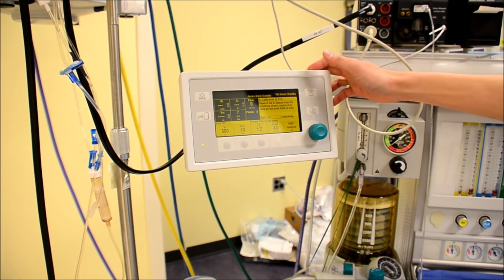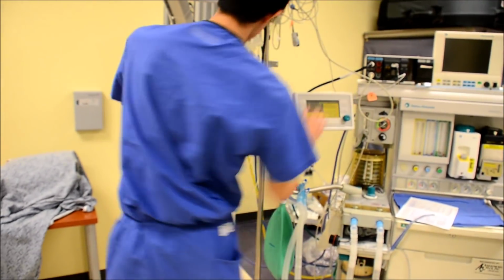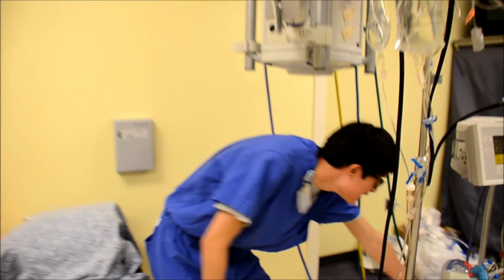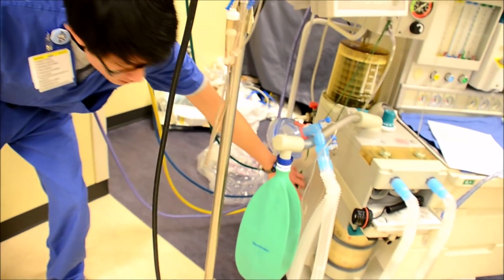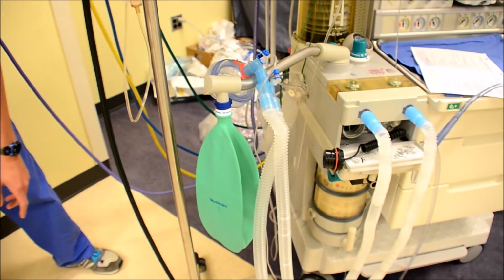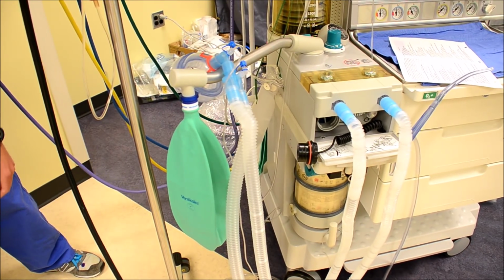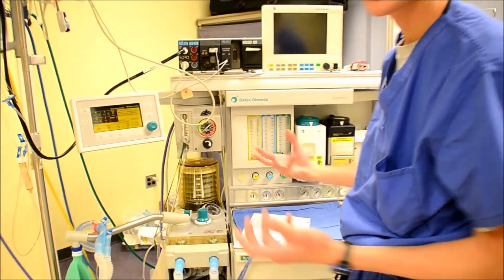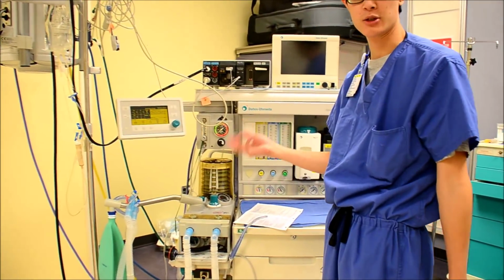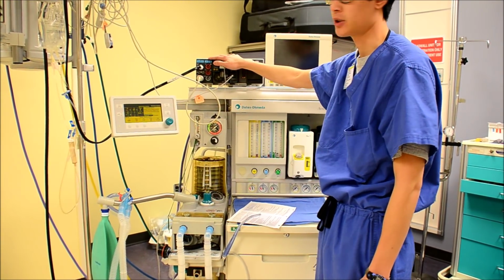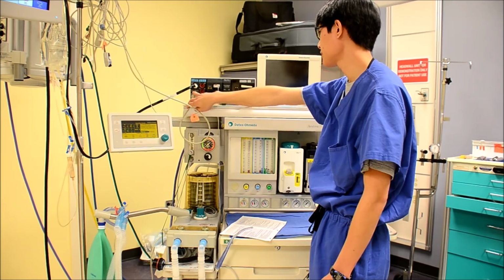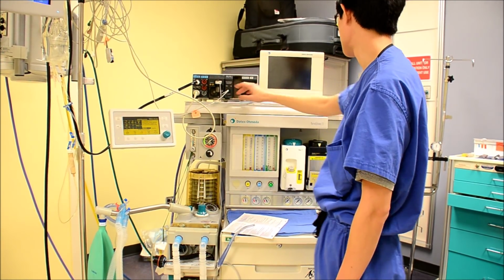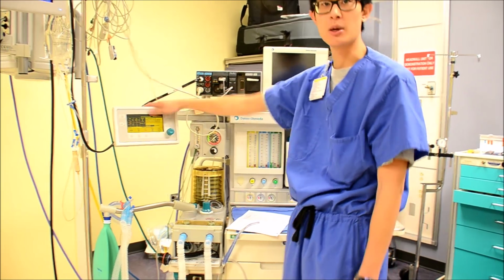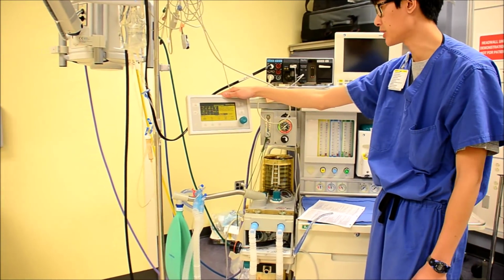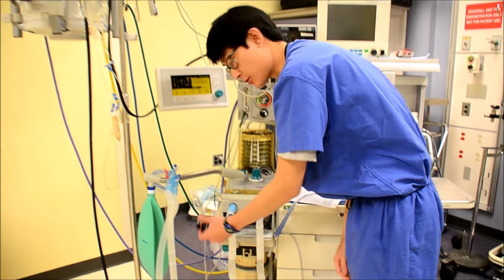So during this time you can check to make sure your scavenging system is working correctly. And there's usually a metal ball on the side. What that tells you is there's adequate amount of pressure of suction. So we'll check that. And at this time, usually I can set up my airway, my blades, my handles, my tube, and a good time to check and make sure you have your adequate monitors. So we have blood pressure cuff, EKG, end tidal, SpO2, train of 4, and so by the time that's finished, it's completed calibrating. So you can go ahead and replace this back in.